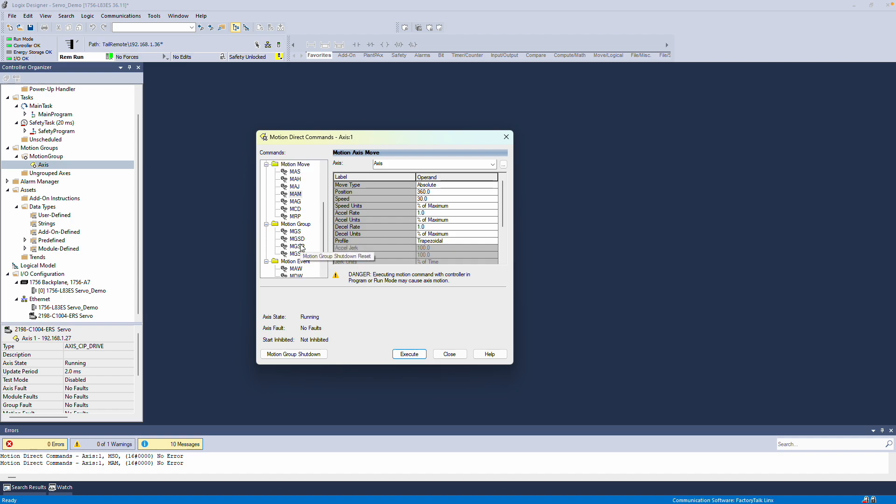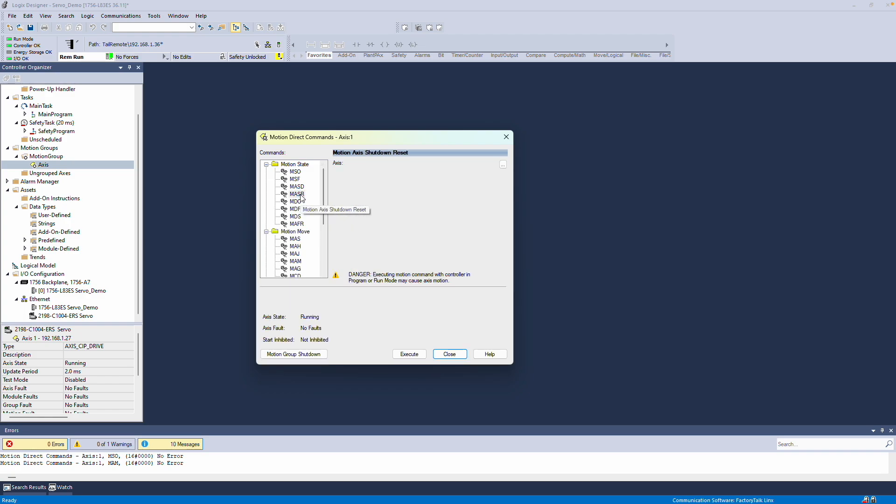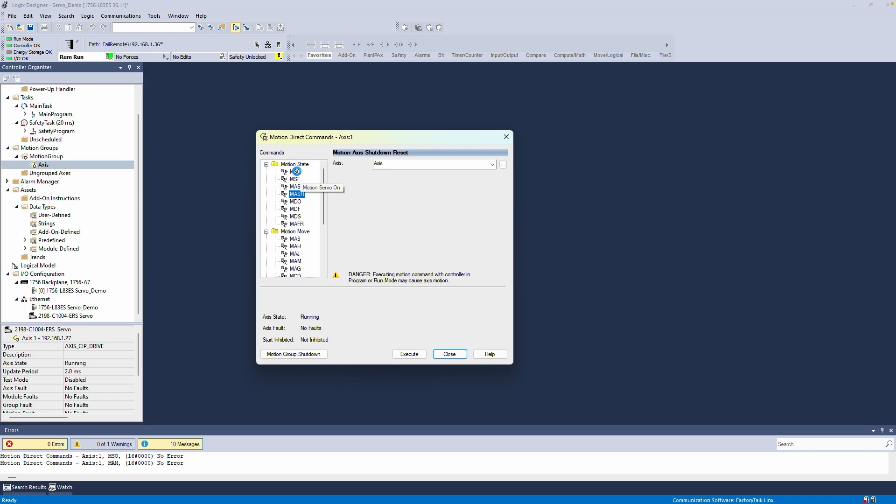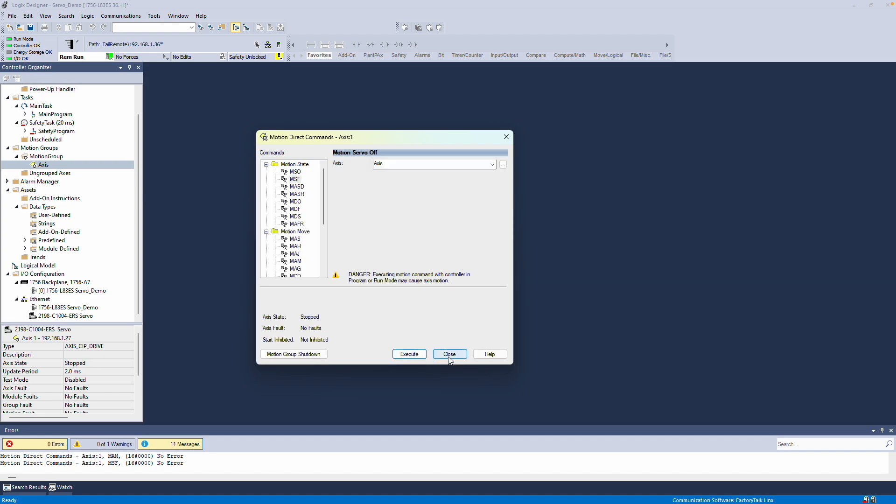There are many other commands available here, all of which are also accessible as instructions in the PLC. If your servo drive ever faults, you'll need to use the Motion Axis Shutdown Reset command. This command will shut down and reset the servo drive. After running this command, you'll need to run Motion Servo On again. If you want to turn off your servo, you can use the Motion Servo Off command, which will power it down.